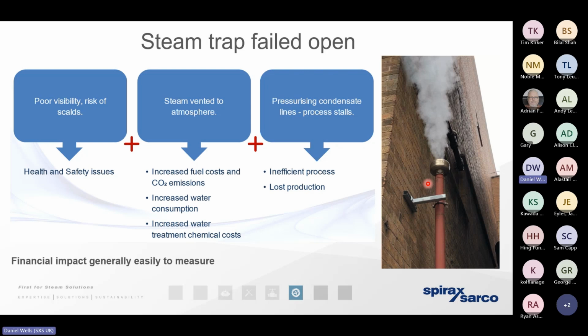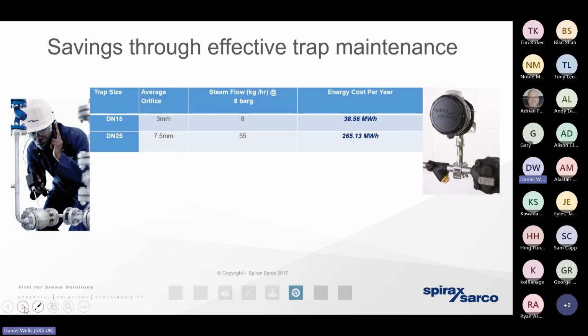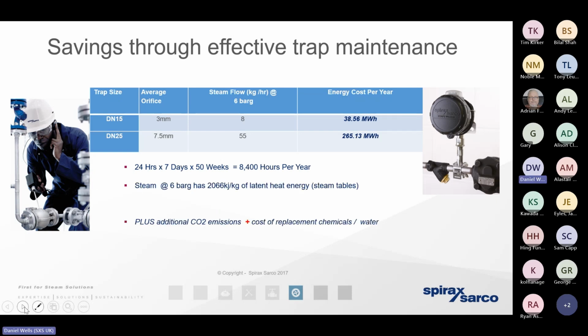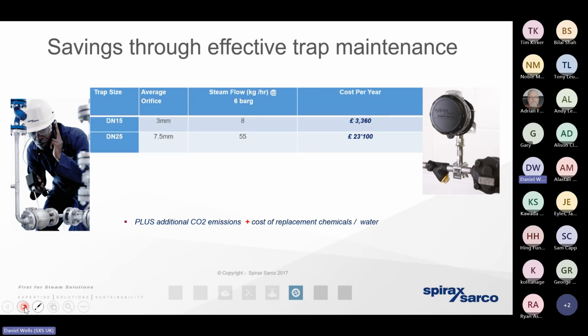So over towards the right hand side of the screen, you can see what the implication is. It means that we're going to have a visible plume of steam venting away until such a time that they can be repaired. And every steam trap type has got approximately the same orifice size. So if we know the trap type, size, and the steam pressure, we know approximately how much energy is being lost whilst that trap is left in the fully open position. So we can quantify what that energy loss looks like, either in terms of energy, or if we've taken that further step and calculated our cost of steam, we can then understand what that single trap is contributing in financial loss over a 12-month period or until such time it's repaired or replaced.